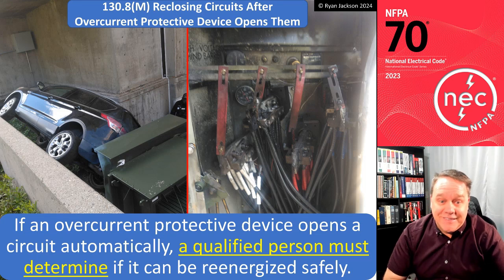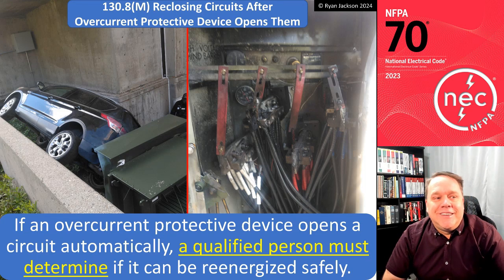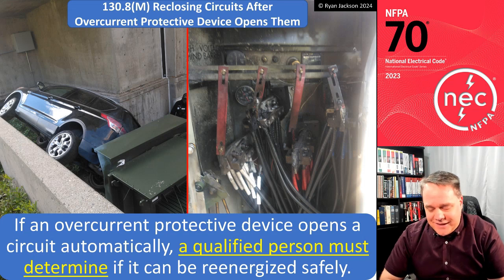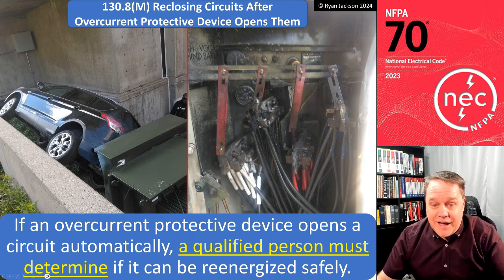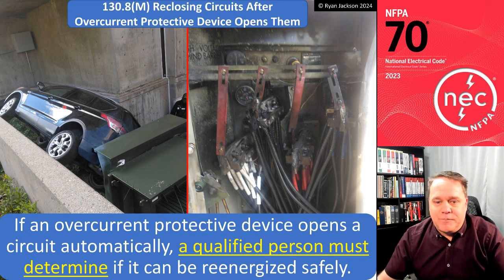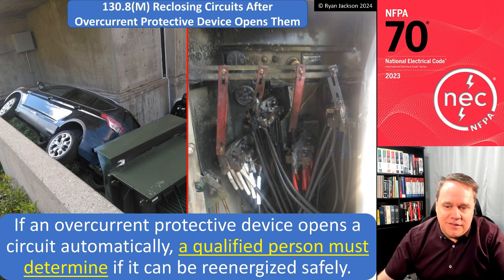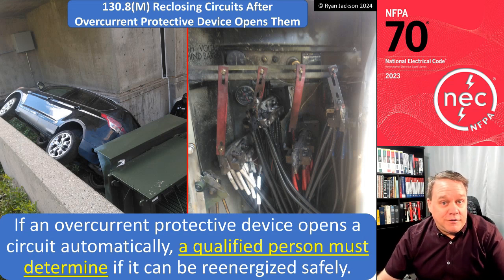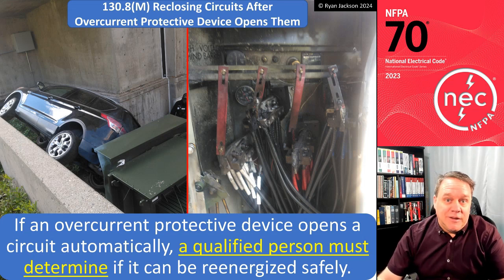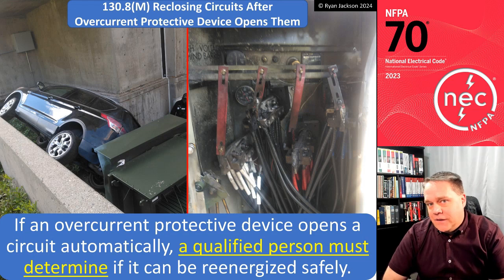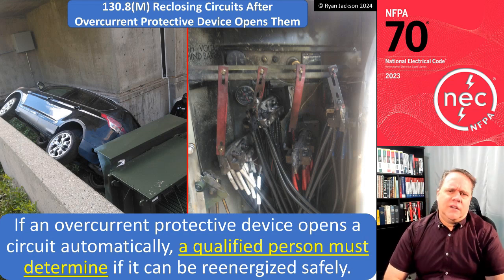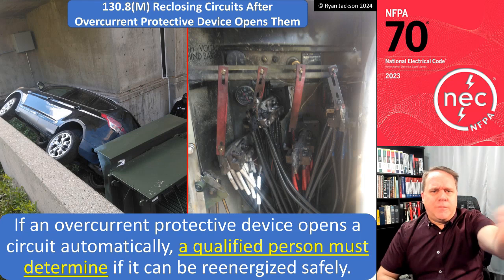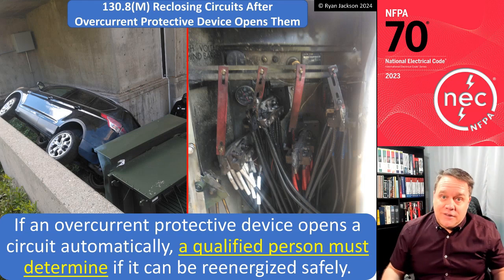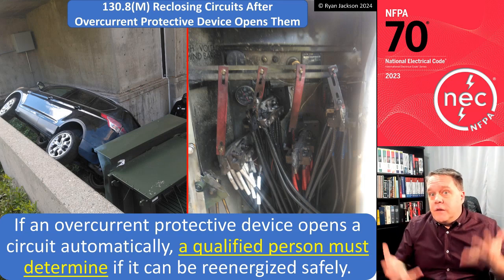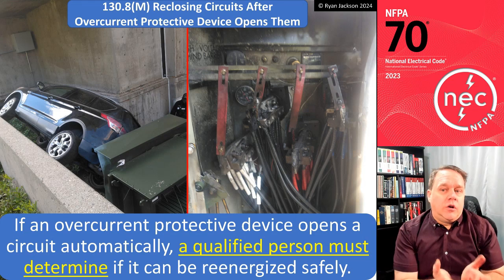I can just tell you that it did. This is at a facility where I teach every year, and they show me this series of pictures where somehow this car ended up smacking into this transformer and blew the transformer into smithereens. Did a circuit breaker or a fuse open when that happened? Absolutely. Would it be prudent to just walk up to that and say, wonder why that breaker tripped? Let's keep on figuring it out until, right? No. If the breaker tripped, we need to figure out why before we start resetting it.